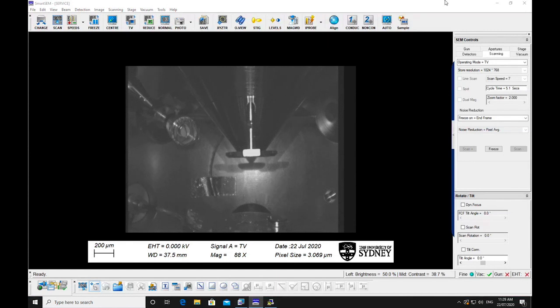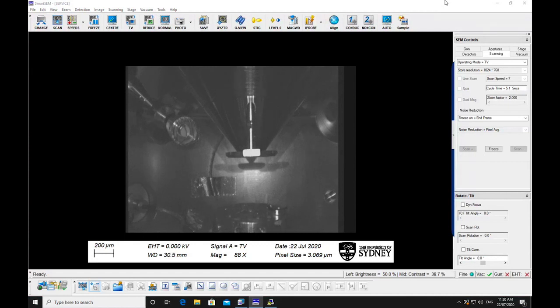Roughly position your sample under the pole piece. Move the stage up so that the specimens are about half way up the screen, while keeping the chamber camera view on.